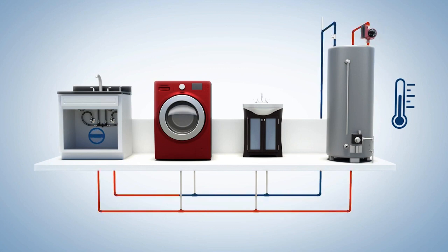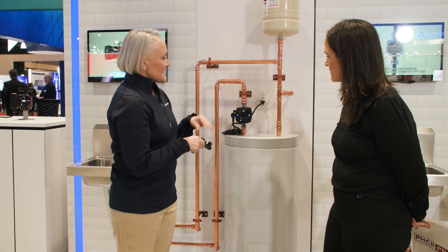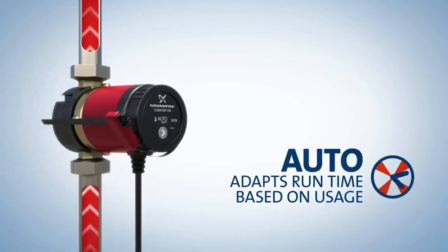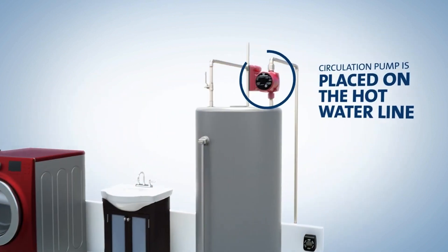Our valves are sophisticated — there's a paraffin element that squeezes the valve shut. If the pump recognizes that this valve is closed, it won't come on, because it's warm enough and we don't need to heat it. There's always a protocol that overrides it for efficiency. This pump recognizes a call for heat within a window of 95 to 102 degrees. It will come on, learn your system through the auto-adapt feature, and continue to drop by a tenth of a gallon until it finds where your system needs it to be — slowing down to exactly the GPM needed to maintain that temperature control. And again, if the valve is satisfied, it doesn't come on.